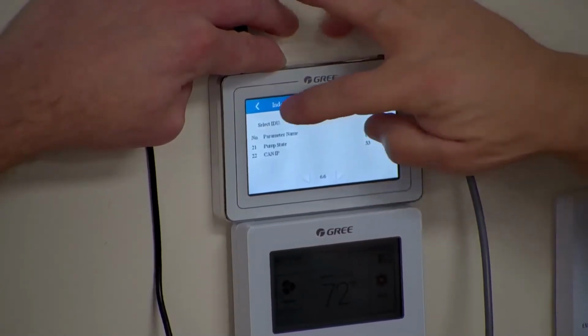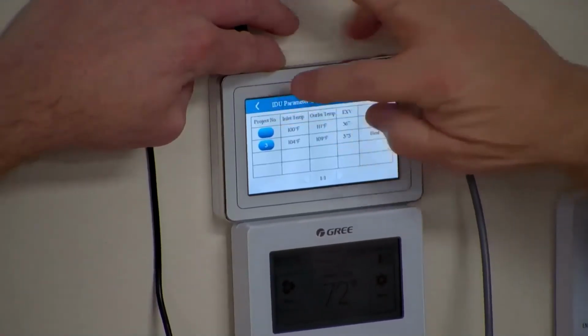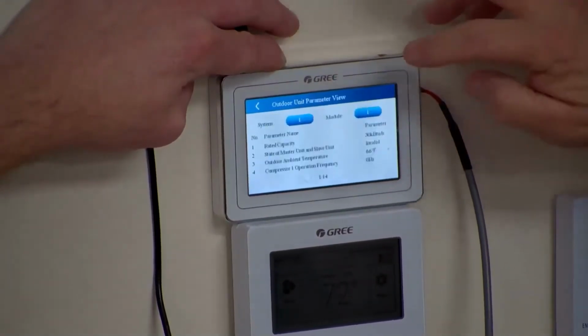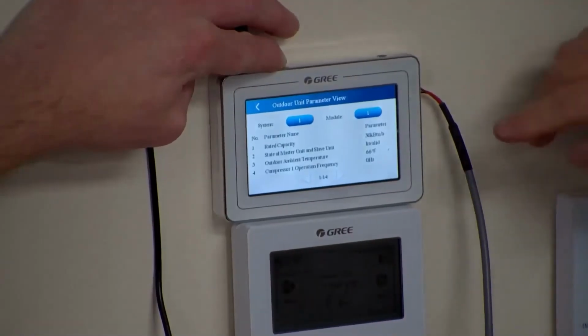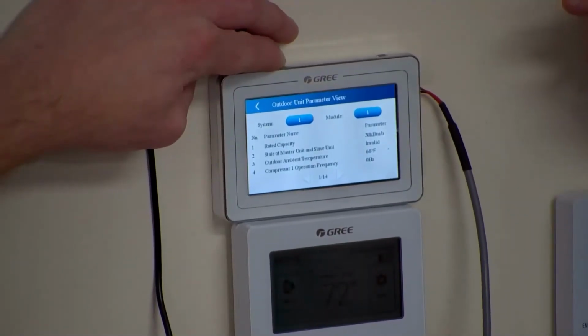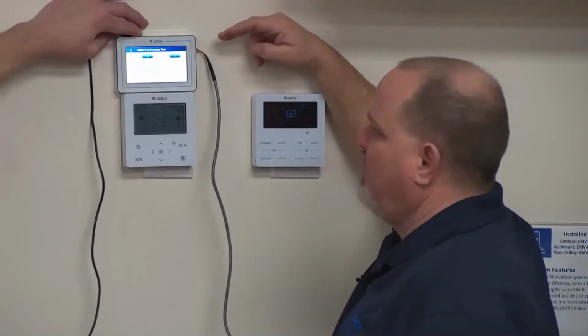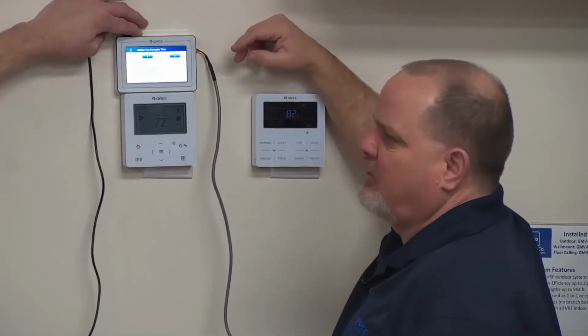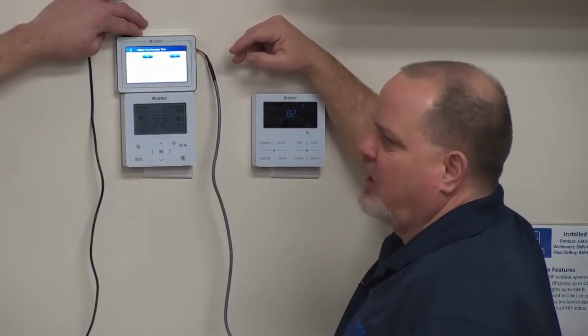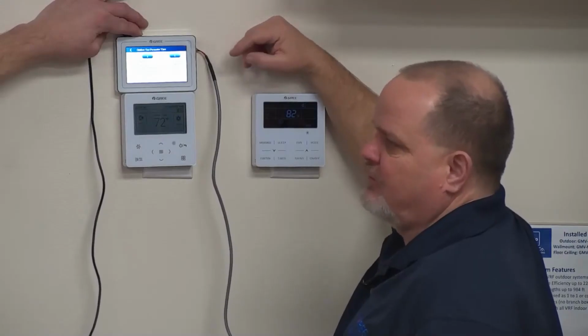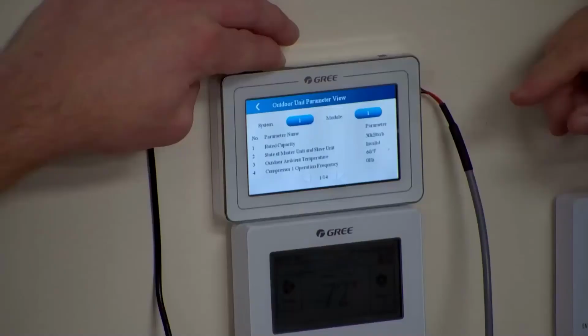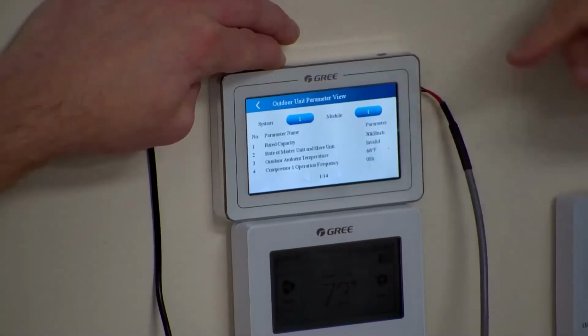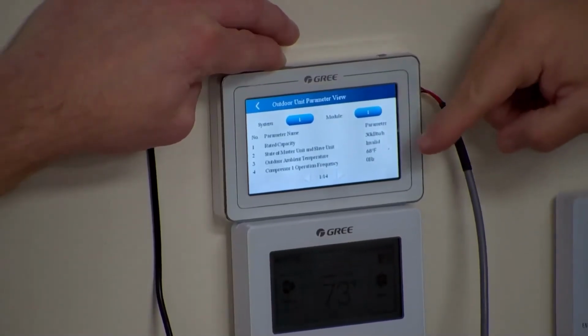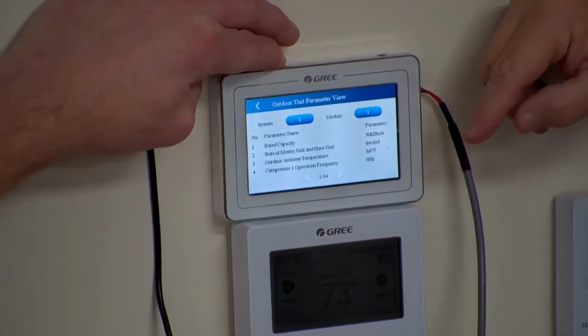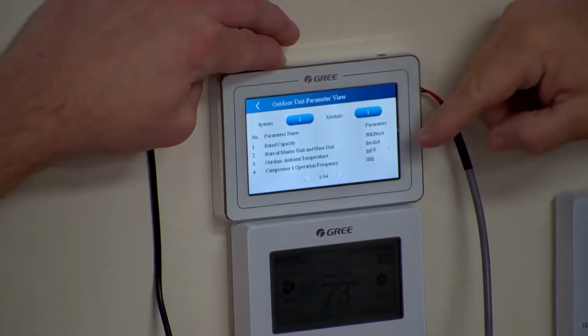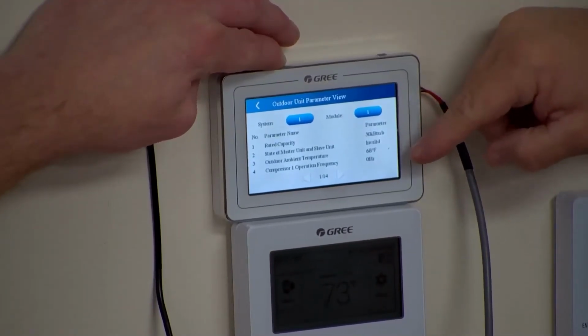Cool. Now let me go back. We can also look at our outdoor unit status. Keep in mind, this is the same service tool. If I went and hooked up to a 3-phase heat recovery unit, I can view up to 66 indoor units with the same service tool. That's why it's saying compressor number 1 operating frequency 0. We obviously know the compressor is running, so give me just a second, we'll get there. Rated capacity 30,000 BTUs.